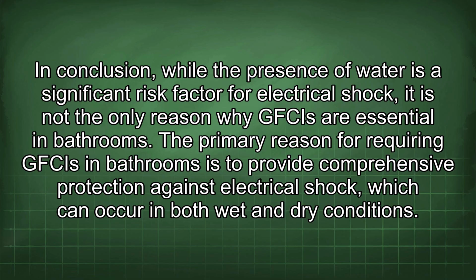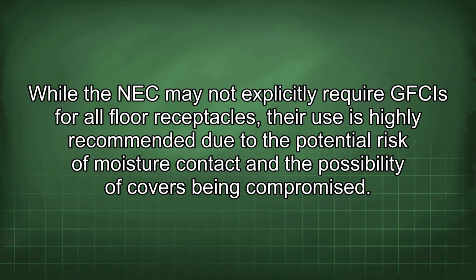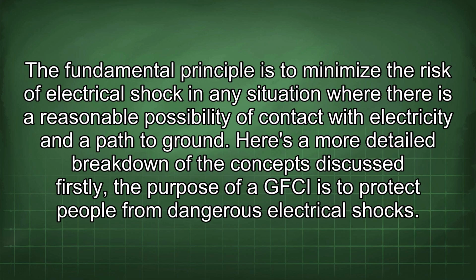In conclusion, while the presence of water is a significant risk factor for electrical shock, it is not the only reason why GFCIs are essential in bathrooms. The primary reason for requiring GFCIs in bathrooms is to provide comprehensive protection against electrical shock, which could occur in both wet and dry conditions. While the NEC may not explicitly require GFCIs for all floor receptacles, their use is highly recommended due to the potential risk of moisture contact and the possibility of covers being compromised. The fundamental principle is to minimize the risk of electrical shock in any situation where there is a reasonable possibility of contact with electricity and a path to ground.